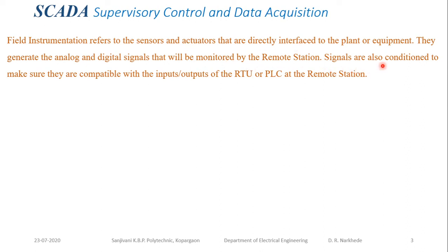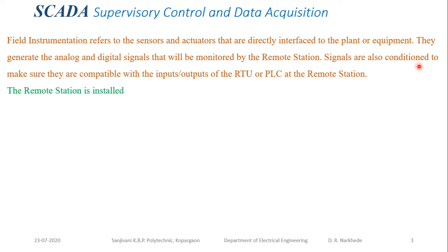Signals may have low strength or be weak, or sometimes may be too strong. There may also be noise present. So we use a signal conditioning circuit to condition the signals and make them compatible with the input/output of the RTU. RTUs and PLCs are designed to operate on DC signals — typically 12V, 24V, or 48V, with 12V and 24V DC being most common. Whatever the signal strength, it is converted into a signal compatible with the RTU or PLC.